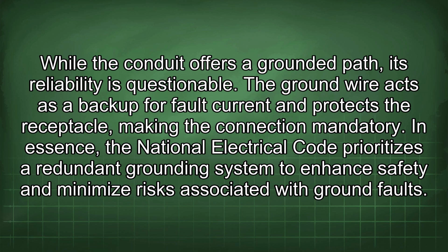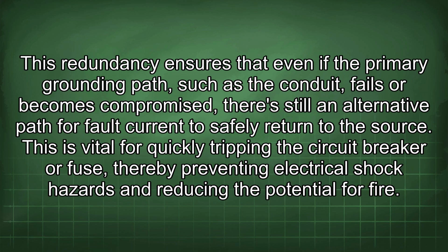In essence, the National Electrical Code prioritizes a redundant grounding system to enhance safety and minimize risks associated with ground faults. This redundancy ensures that even if the primary grounding path, such as the conduit, fails or becomes compromised, there's still an alternative path for fault current to safely return to the source. This is vital for quickly tripping the circuit breaker or fuse, thereby preventing electrical shock hazards and reducing the potential for fire.